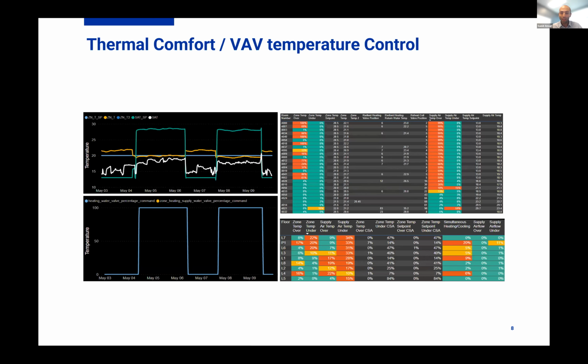Our air handling unit supply air temperature was locked at 17 degrees. Our VAVs were trying to discharge 13 degrees supply air to cool down the space. So kind of creating cooling out of nothing, with no coils. Again, this is part of the issue that happens when systems are not looked at together. They're looked at individually. There's a specific checklist, and you just try to go through that checklist. Or sometimes you even do a random sample check. You're not going to go through hundreds and hundreds of VAVs, terminal units, trying to commission all those in person.